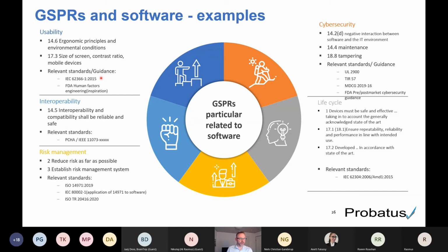If you are planning to go for the US, you need to be careful here, because the FDA human factors engineering guidance document, which is quite good for inspiration, explicitly requires 15 people in each distinct user group. This could be doctors, nurses, and home care users. Could be 3 user groups for one device, and you need 15 in each of these user groups. So that's a lot of people to involve in this usability evaluation.